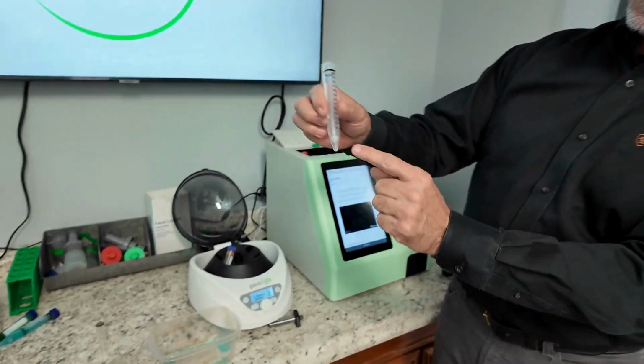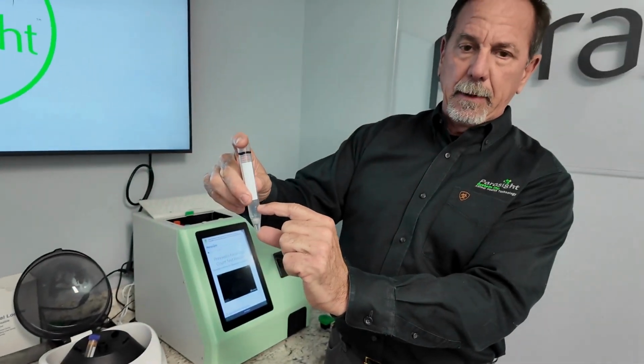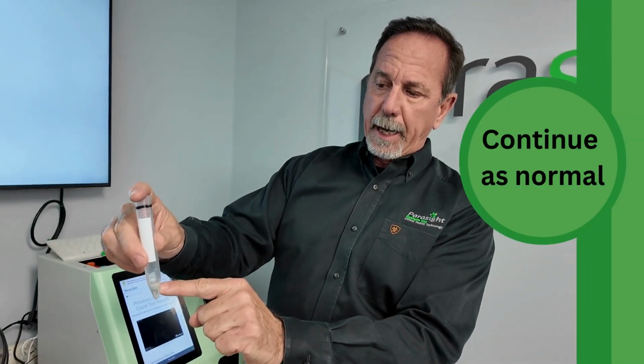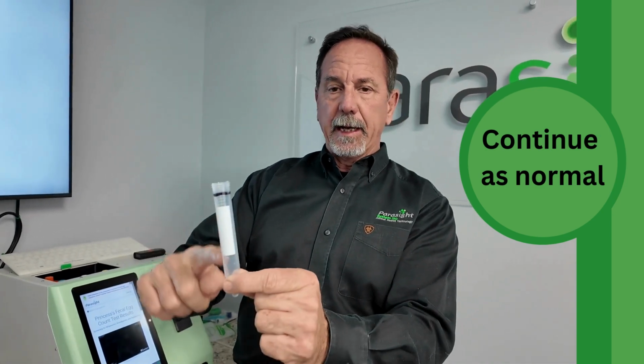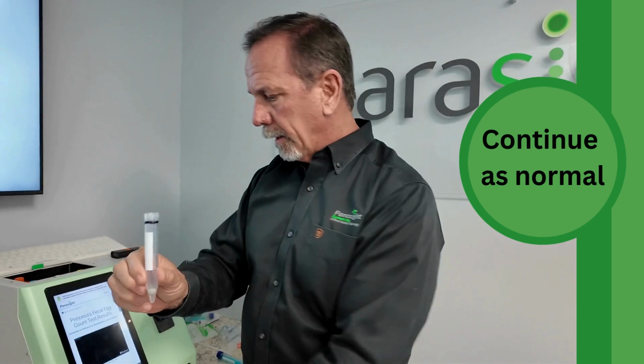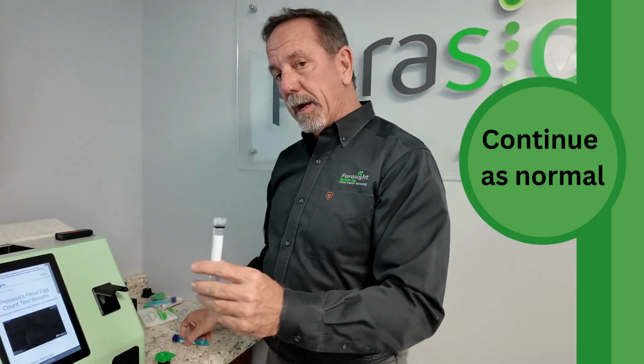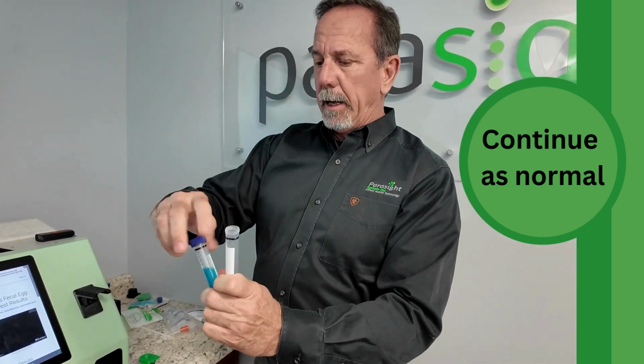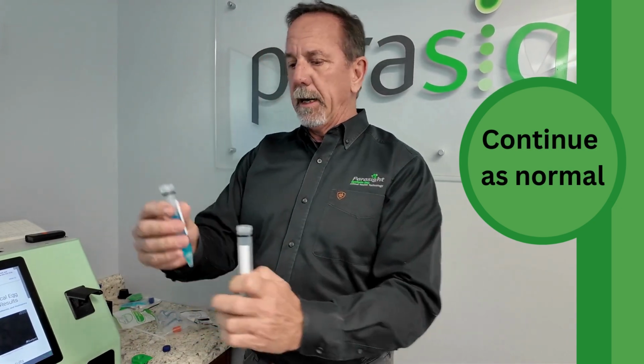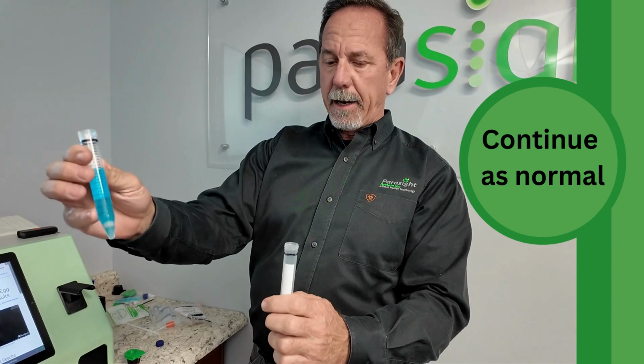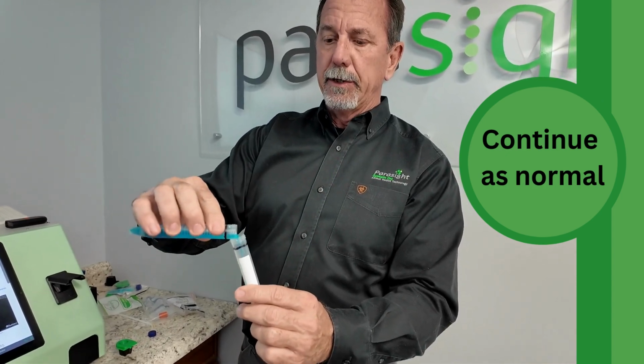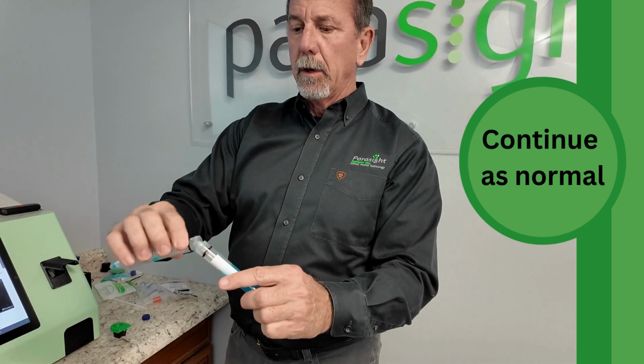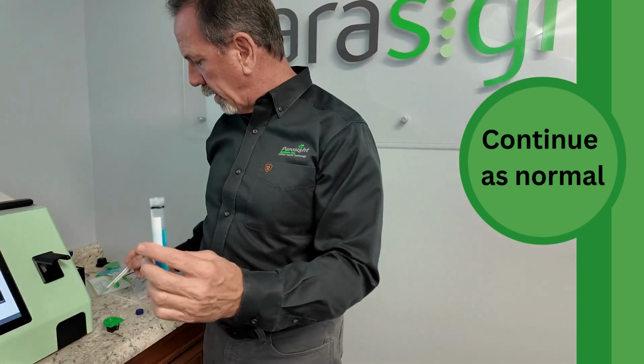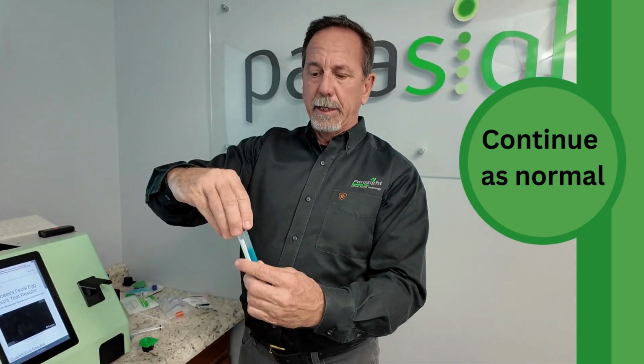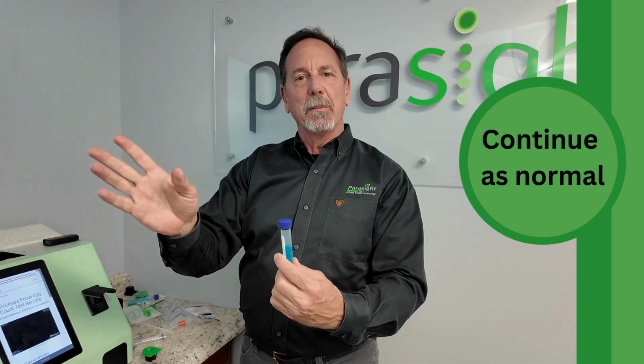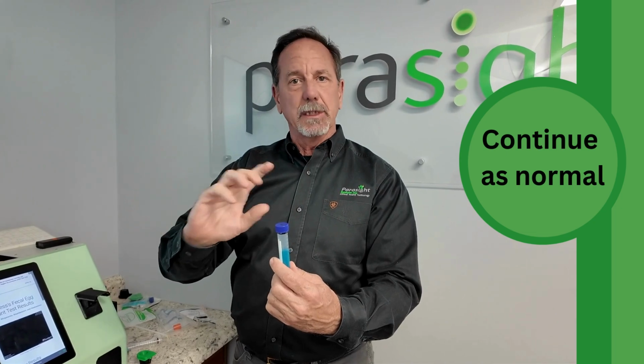So all you'll do is you'll have a pellet at the bottom, along with the agitator here, and you'll have nothing else in there. Okay? Then what you're going to do is you're going to open up another pack, and you're going to go ahead and borrow the colored Fecasol out of that pack, and you're going to pour it back into this one without the ball. Now what you get to do is we're going to do the same thing we'd normally do, like there's no mucus in this, just like we started over.